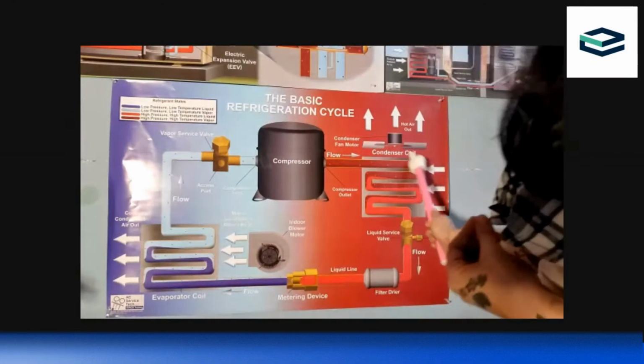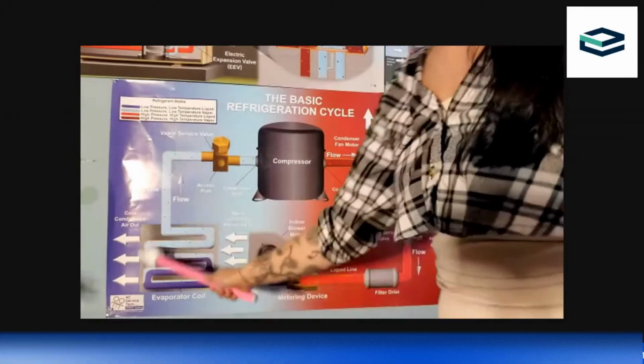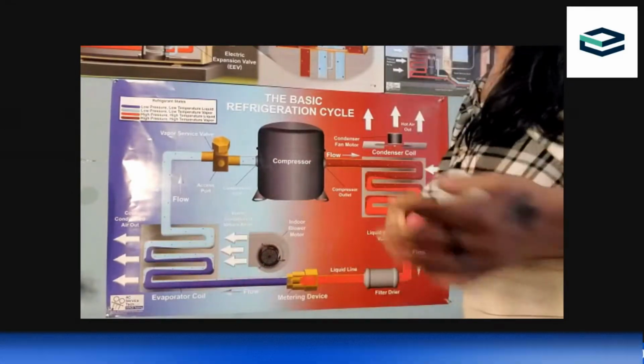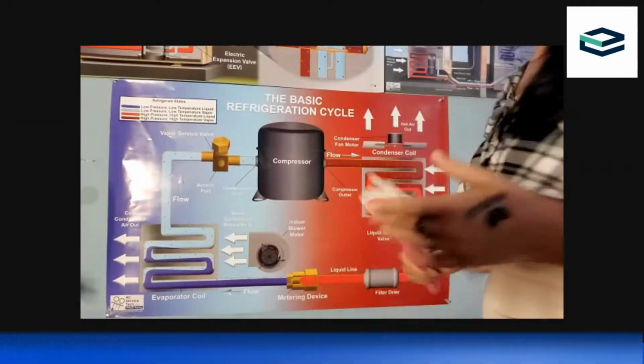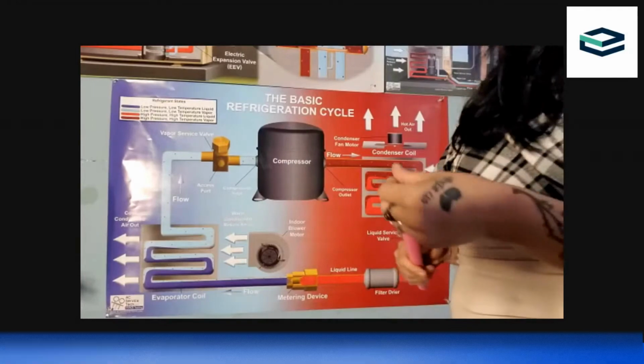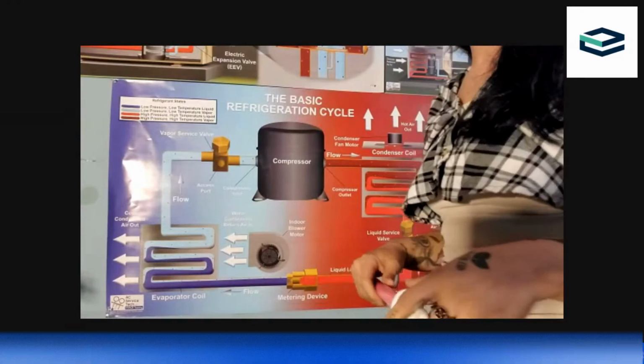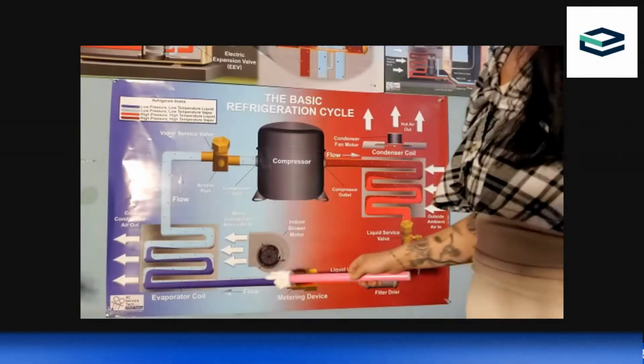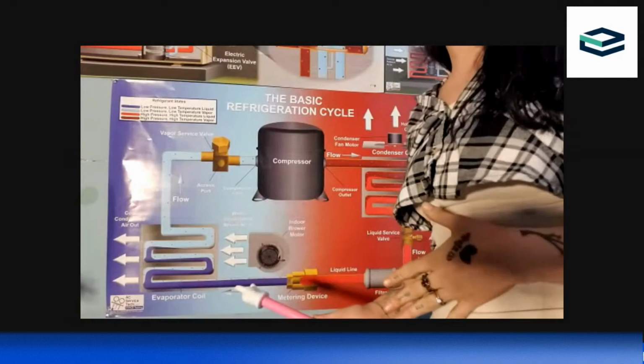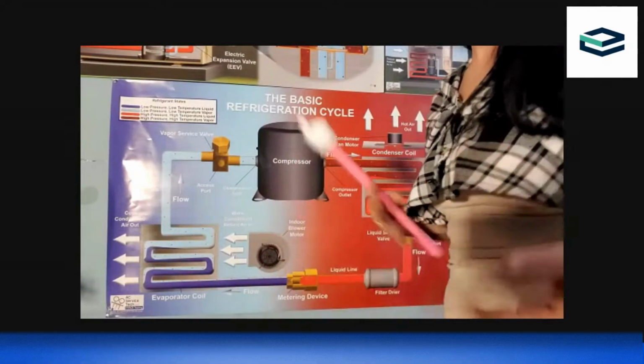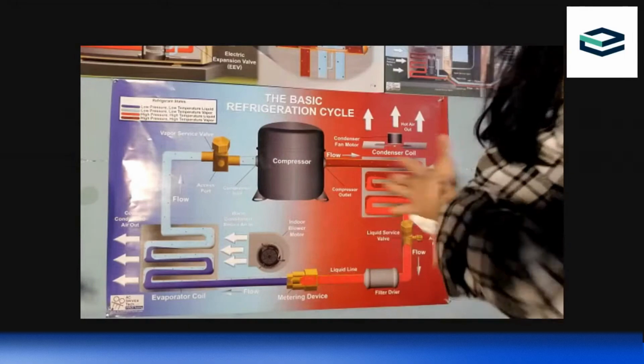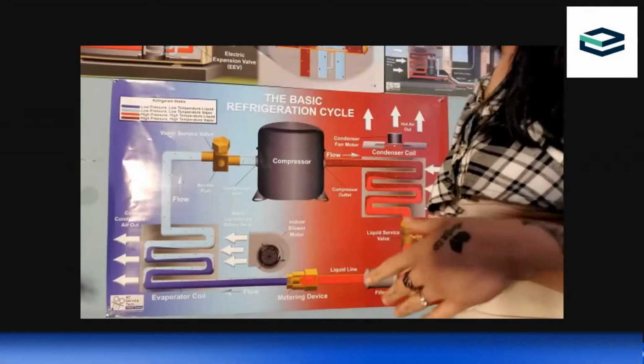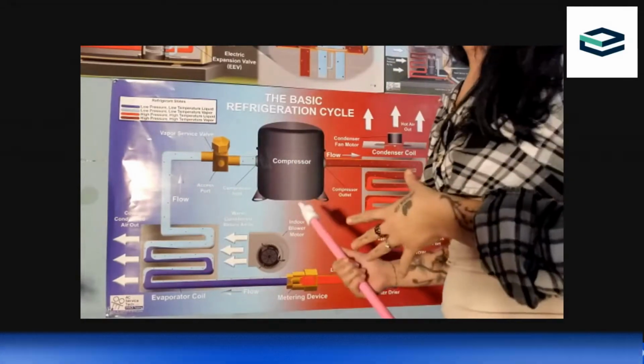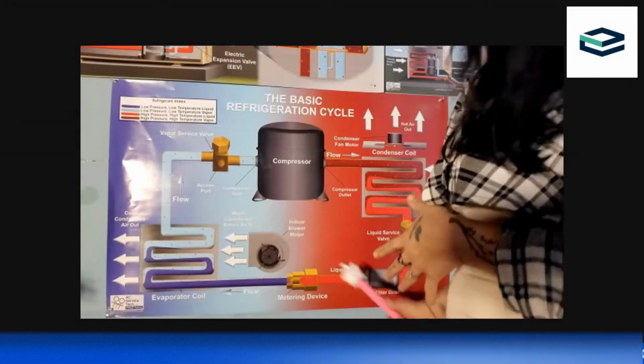And then where the condenser condenses, the evaporator evaporates. So you can think of it in forms of water, but the temperatures are so very different. Where water boils at 212 degrees, we are not getting that with refrigerant. Most refrigerants actually evaporate in negative degrees Fahrenheit. So because of that, the temperature of a room is almost always warm enough for it to evaporate, right? So if you have a 74-degree room and your refrigerant evaporates at negative 50 degrees, then your room, no matter what, is going to be enough load to evaporate.